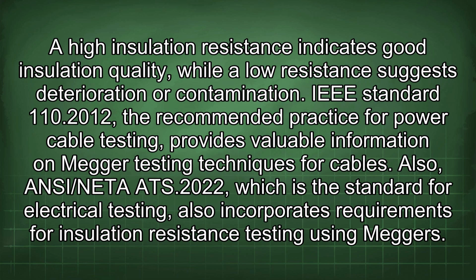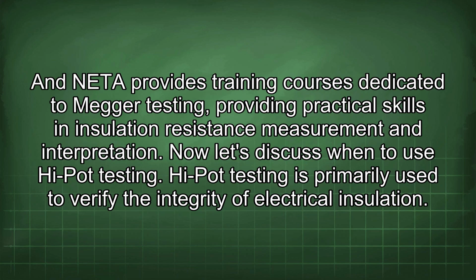IEEE Standard 110.2012, the recommended practice for power cable testing, provides valuable information on Megger testing techniques for cables. Also, ANSI/NETA 2022, which is the standard for electrical testing, incorporates requirements for insulation resistance testing using Meggers. And NETA provides training courses dedicated to Megger testing, providing practical skills in insulation resistance measurement and interpretation.